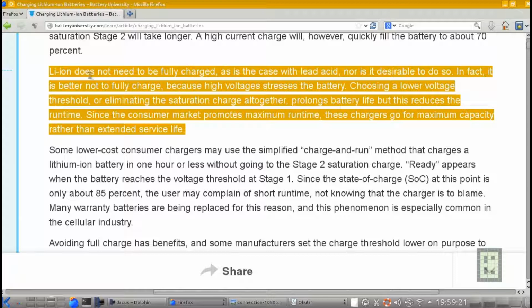Like you see here, lithium ion doesn't need to be fully charged, as is the case with lead acid, nor is it desirable to do so. In fact, it's better not to fully charge, because high voltage stresses the battery. Choosing a lower voltage threshold, or eliminating the saturation charge altogether, prolongs battery life, but this reduces the runtime, meaning the available capacity.